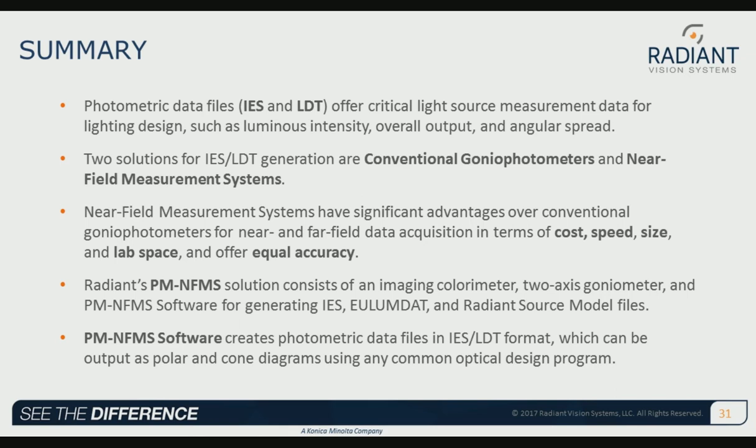Two solutions for IES LDT file generation are conventional goniophotometry and the near-field measurement system. The near-field measurement system has some significant advantages over conventional goniophotometers for near and far-field data acquisition in terms of cost, speed, size, and lab space, and offers equivalent accuracy.